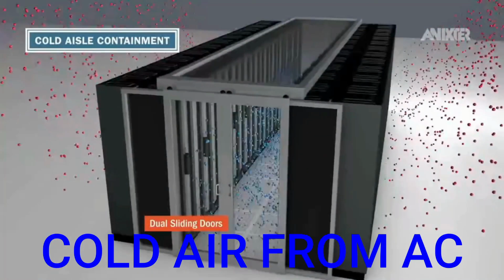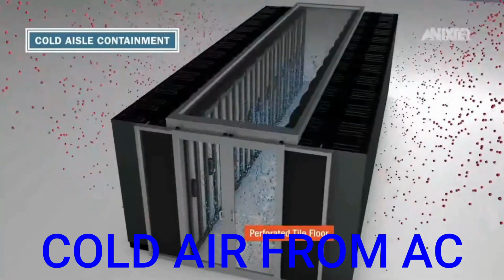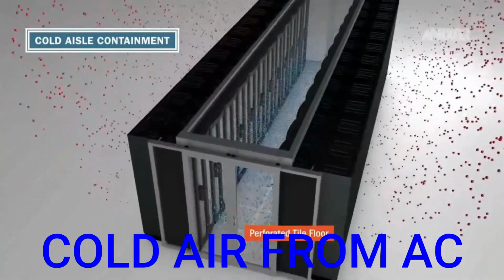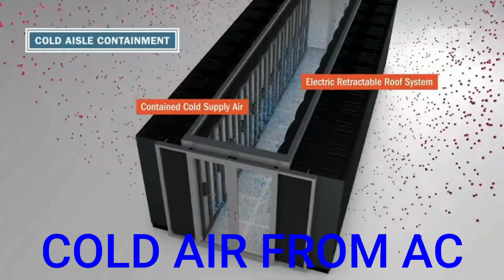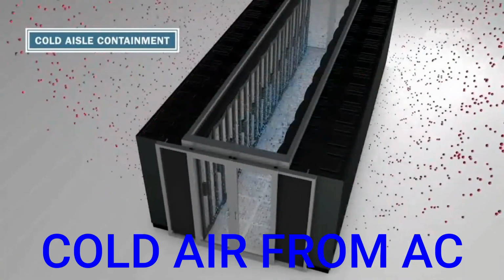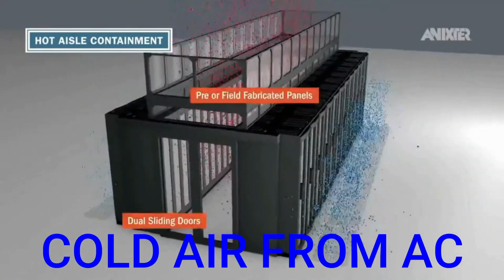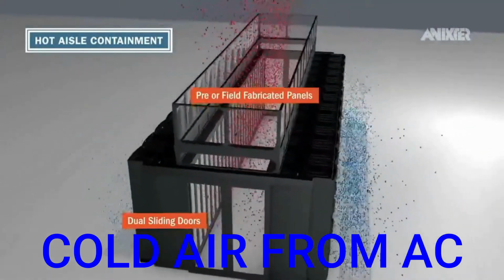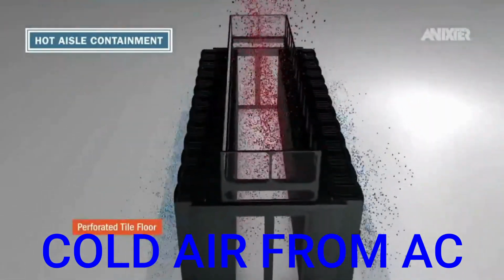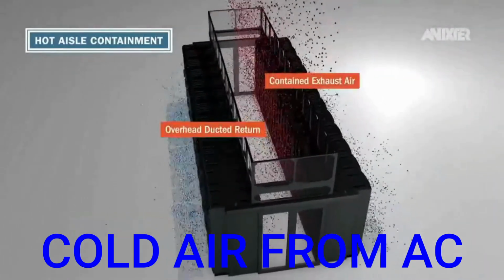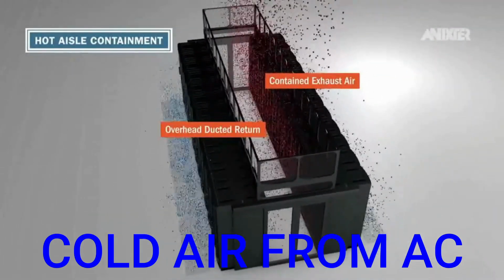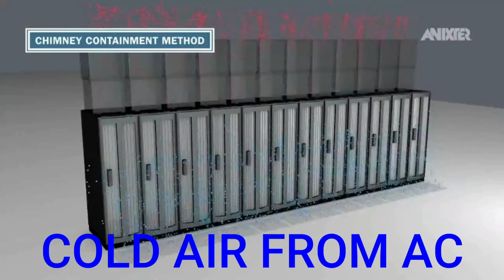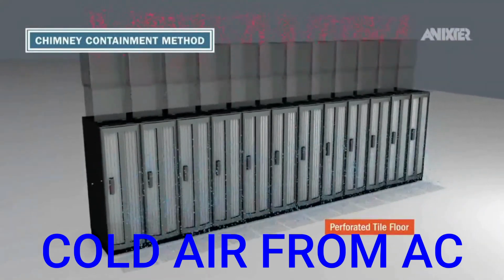You don't have to cool the whole area, just the front of your servers. In this scenario there are two types of exhaust setups. One has the hot aisle in the middle with cold air coming from outside, which is most common now in warehouses. The other is vice versa, with cold air in the middle and exhaust going outside.